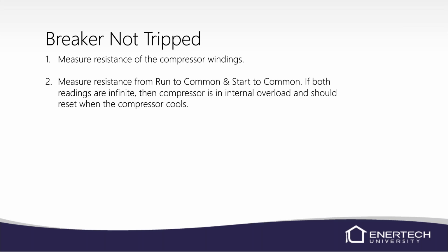Measure the resistance of the compressor windings across each other. Measure the resistance from run to common and start to common. If both readings are infinite, then the compressor is in internal overload and it'll reset when the compressor cools. If it's not hot, it could be it got hot one too many times and it will not reset. It may reset, but more than likely it'll trip again. So don't just reset it and walk away.